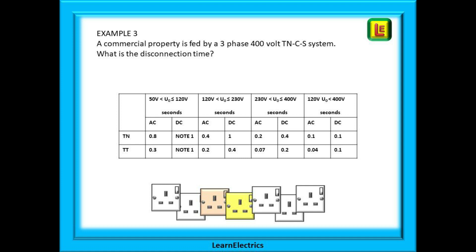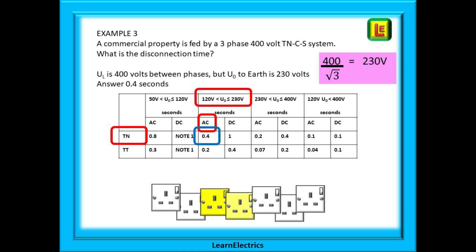Example 3 is for a commercial property fed by a three-phase 400 volt TNCS system. 400 volts is the voltage between lines, called UL not U0. U0 is calculated by dividing the line-to-line voltage of 400 volts by the square root of 3 — in other words, 400 divided by 1.732 — which gives us 230.9 volts, rounded down to 230 volts. So for a 400 volt three-phase system, U0 is 230 volts. Choose a row, choose a voltage range, and the disconnection time is 0.4 seconds.